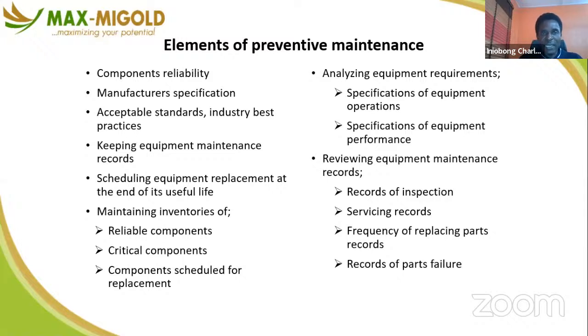And they want to see if you followed the manufacturer's specification. Acceptable standard, industry best practice. You follow acceptable standard - for generators, a good new generator, you want to run it for 250 hours before servicing, which is best practice. But if you have very old generators, it's better you put it around 200 hours so that it will reduce the downtime, unplanned downtime.